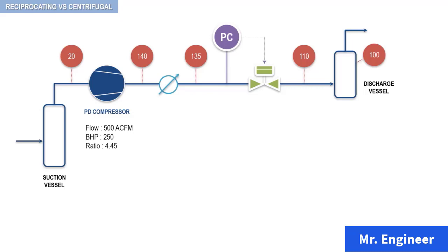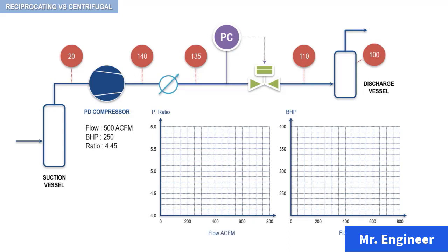Let's now plot the actual cubic feet per minute versus pressure ratio, and the actual cubic feet per minute versus brake horsepower. In this example, the actual cubic feet per minute is 500 and the pressure ratio is 4.45. So here you have your first operating point. And for the brake horsepower, we have 500 cubic feet per minute as flow and 250 brake horsepower.